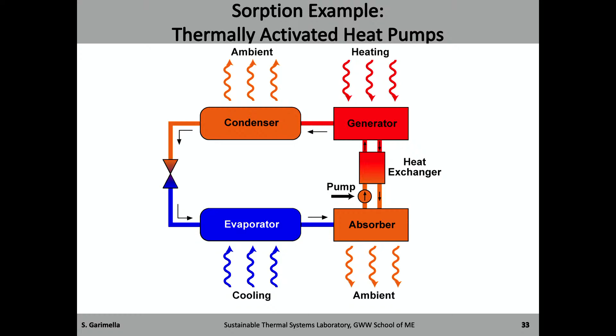You supply whatever heat you have available, whether it's natural gas, solar, or waste heat, and use that as the heat source. You boil off the refrigerant, condense it, expand it, evaporate it, just like in a regular cycle, then mix it back into the absorber, and now you're pumping a liquid, not a vapor, up. So this is versatile, and the working fluids don't have global warming potential, but you've replaced one compressor with three heat exchangers, and that, for residential applications, used to be a challenge because it needs much more surface area.